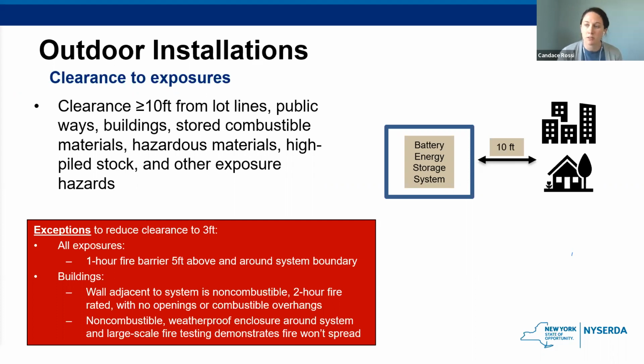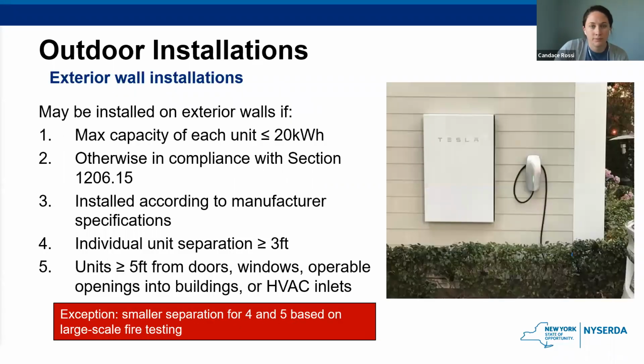So there are different exceptions to certain requirements throughout the code. And then additionally, if the outdoor installation is being installed on an exterior wall, the system may be installed on exterior walls if the max capacity of each unit is under 20 kilowatt hours. Otherwise, they'll have to meet compliance with section 1206.15. They have to be installed according to the manufacturer specifications. The individual unit separation must be greater than 3 feet. Units must be greater than 5 feet from doors, windows, operable openings into buildings, or HVAC inlets. And once again, there might be the possibility for smaller separation for 4 and 5 based on large scale fire testing.